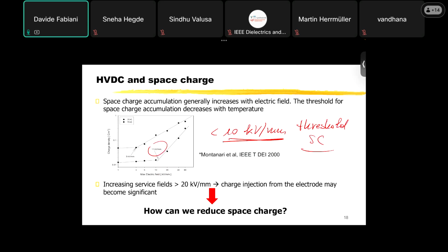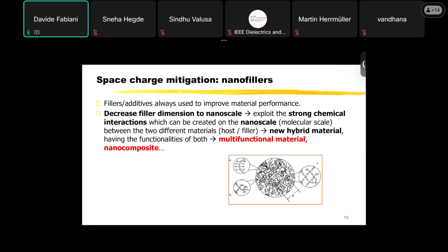The problem is that we want to increase the service field because we are increasing the voltage of our electrical applications. So the field is now larger than 20 kilovolt per millimeter. But as you can see here, if you increase the field, you will increase the space charge that is accumulated in your material. So how can we do? How can we reduce the space charge while increasing the electric field? There are many techniques. One is mitigating space charge by using nanofillers.